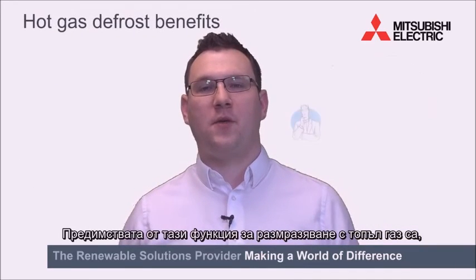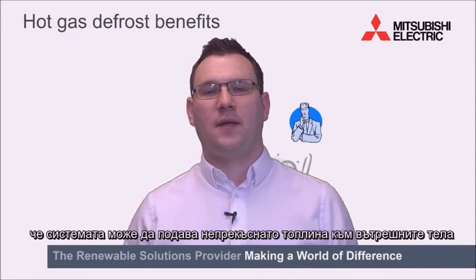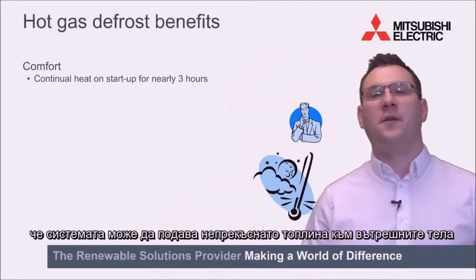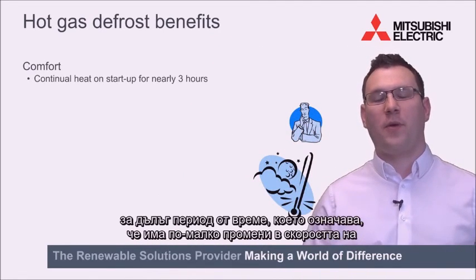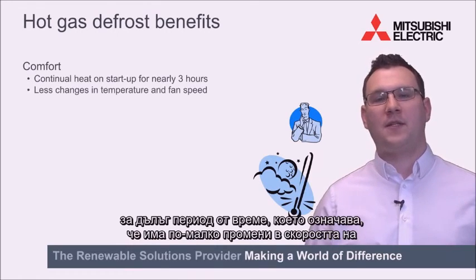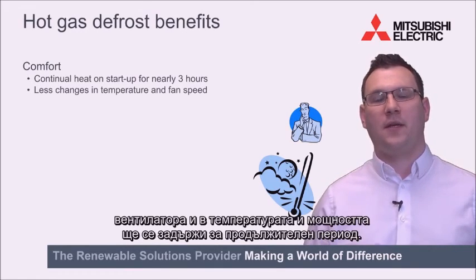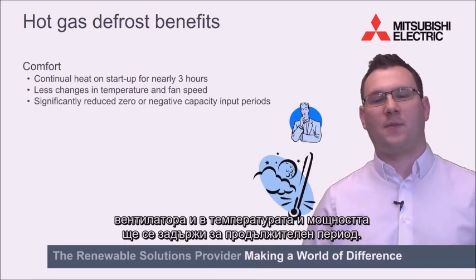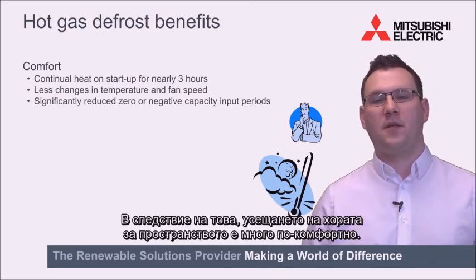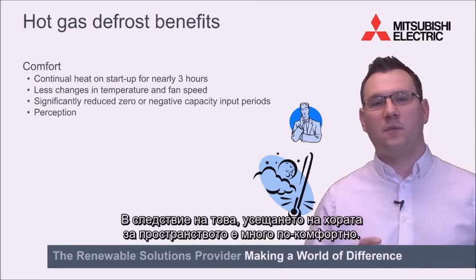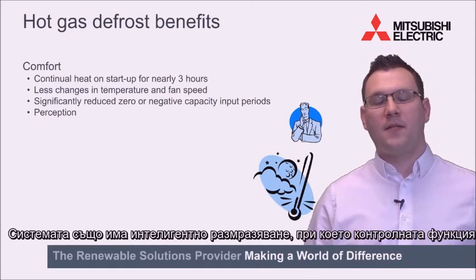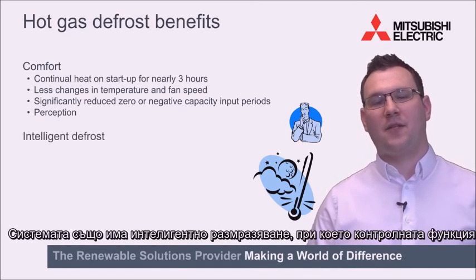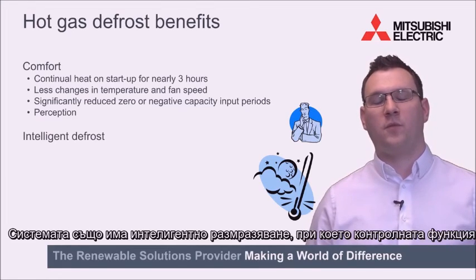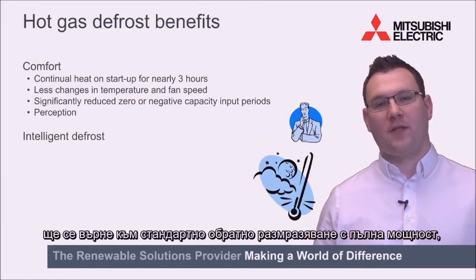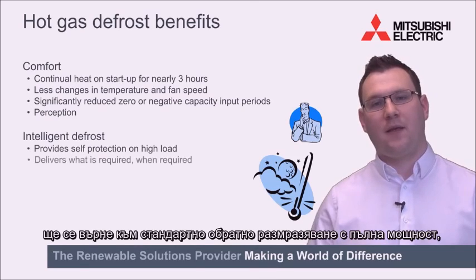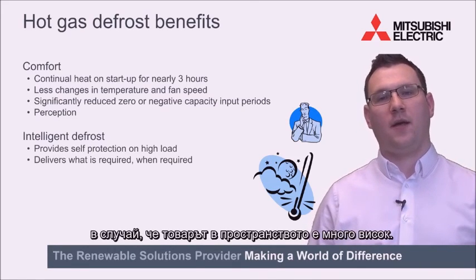The benefits of this new hot gas defrost function are that the system can deliver continual heat to the indoor units for a very long period of time, meaning there's less changes in fan speed and temperature, and capacity is actually delivered into that space for a continual period. So the perception of people sat in that space is it's much more comfortable. The system also has inbuilt intelligence defrost, where a control function will revert back to a standard reverse defrost, giving full capacity if the load in the space is very high.